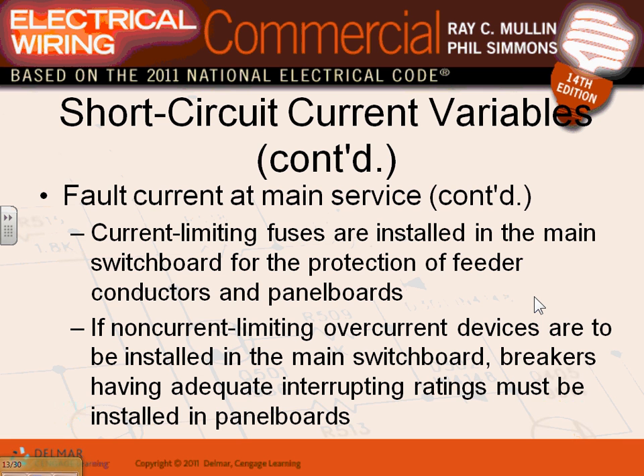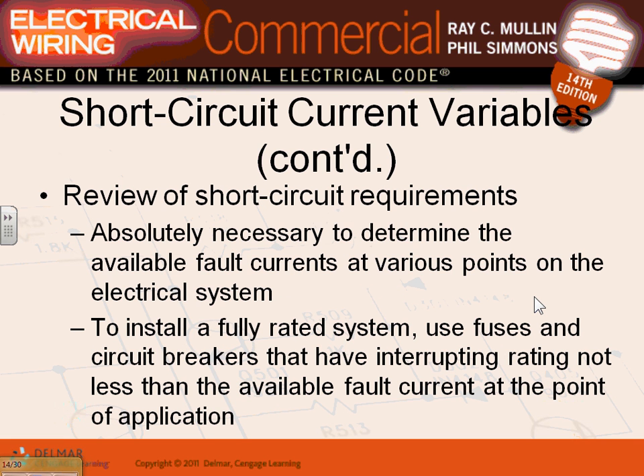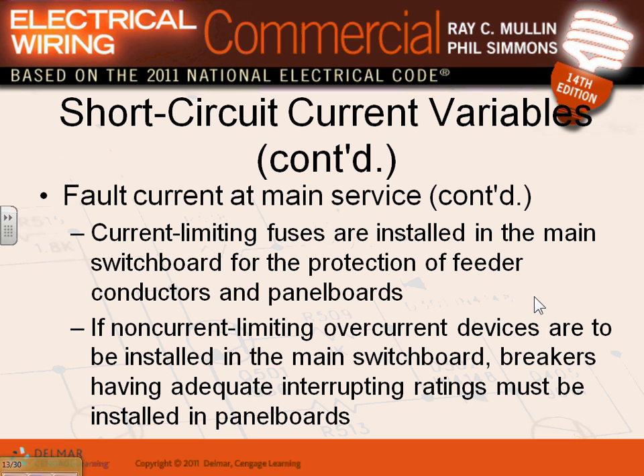Okay, this is the calculation. We did that one. Current limiting fuses. If you have current limiting fuses, guys, as we said, they filter the value. So if you have a current limiting fuse like this baby here, and the available short circuit coming here is 63.5 kiloamp, by the time it comes to this area here, it might knock it down to 42 kiloamps, because it trips fast within a quarter of a cycle, and it chokes the current that's coming in. Does that make sense? 63, you get into a current limiting fuse, it knocks it down to almost 42. And we have the circuit to size it.